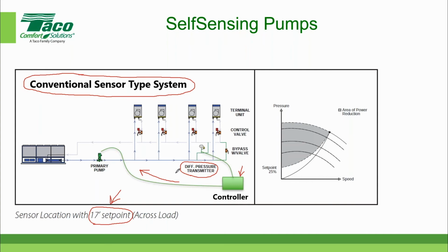And generally speaking, you need to have a differential pressure transmitter, a controller. It has to be hardwired between those two devices. And then you need a control signal, generally a 0 to 10 volt signal out to the variable frequency drive to maintain or change its speed based on what kind of pressure differential you're looking to control to. So before I go on any further, we want to start here because we want to start with a basic understanding of what a conventional sensor type system is.